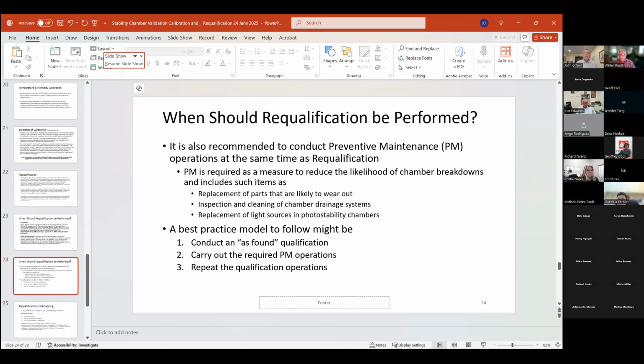It's also recommended to conduct preventative maintenance operations at the same time as requalification. PMs are required as a measure to reduce the likelihood of chamber breakdowns and include such items as replacement of parts, inspection and cleaning, the drainage systems, the air systems as well, and replacement of light sources in photostability chambers. A best practice model to follow might be to conduct an as-found qualification, carry out the required PMs, and then repeat the qualification operations.